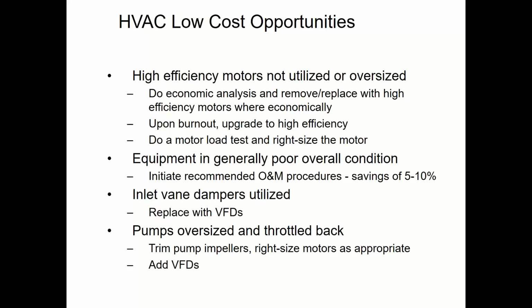It usually doesn't have a good payback to rip out a good motor, throw it away, and put in a more efficient one. However, once the motor does in fact fail or has been tested to be near failure and you have to replace it anyway, you may as well go ahead and put the high efficiency one in, because the difference in cost from regular efficiency to high efficiency motor is very minimal, right? The difference in cost from no new motor to any motor is pretty high, right?